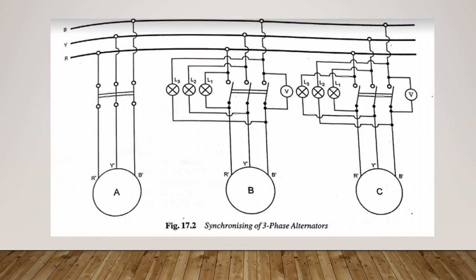For this reason, it is desirable to have two frequencies which are nearly equal so that the synchronizing is not dependent on a constant dark period. The third major disadvantage of this method is that the flicker of the lamps will not indicate whether the incoming alternator is slow or fast. These difficulties can be overcome by using another method called the two bright and one dark lamp method, in which two of the lamps are cross connected.